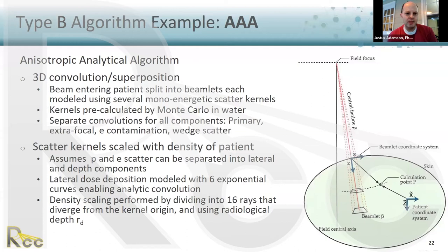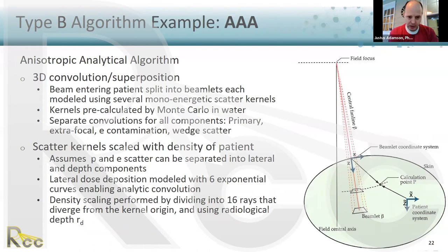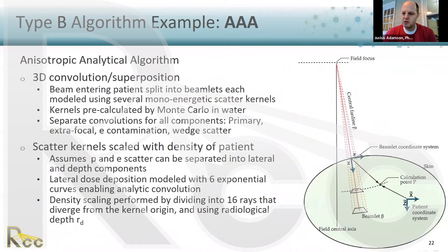Triple-A is a 3D convolution-superposition algorithm. The beam entering the patient is split into beamlets, each modeled with several monoenergetic scatter kernels pre-calculated by Monte Carlo in water. There are separate convolutions for primary, extrafocal, and electron contamination components; wedge contributions are also included. The scatter kernels are scaled with patient density. The lateral dose deposition is modeled with six exponential curves enabling an analytic convolution, and density scaling is performed by dividing into 16 rays that diverge from the kernel origin using the radiological path depth.